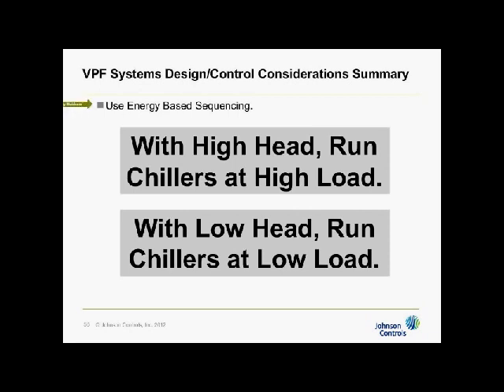Another consideration with VPF systems and design and control is energy-based sequencing. Energy-based sequencing is when you look at what we have typically always used, load-based, and you mix it with energy-based, depending upon conditions that are going on with the weather. When you're at high head, remember to run your chillers at high load, which is load-based type sequencing. When you're at low head, you want to run at low load, which means you want to run 2 chillers to do a 1 chiller job. You want to run 2 pumps to do a 1 pump job, etc. Typically, not always. It depends upon where you are in the pump curve and where the efficiencies lie, but typically you want to run multiple units here and you want to run single units here. Okay?